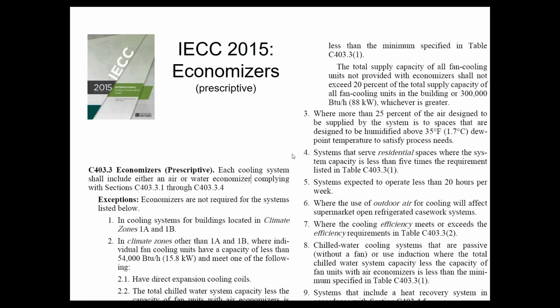So 54,000 BTUs, which is 5 tons and over, needs to have an economizer on it. There are some exceptions, like exception number 3 for certain process applications, exception 4 for some residential spaces in high-rise buildings with chiller systems, exception number 5 would be like a little one-room church where you're only using it Sunday morning and Wednesday night, and that's it. So it's less than 20 hours per week, so you don't have to do the economizer. Chilled beam type stuff, there's a few exceptions like that. But for your normal retail, office, school type stuff, you're going to have to do the economizer.